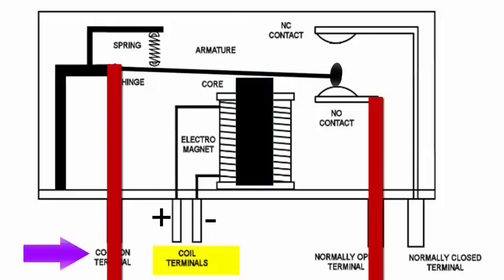It may be used to operate a motor, or a solenoid valve, or some other electrical device. But at the coil terminal, you can get the feedback from the sensors or some small signal only is required over here. But the common terminals are actually carrying the required amount of current. So these are heavy duty, and the wiring and other things over here will be of a lighter duty because not much current is needed.